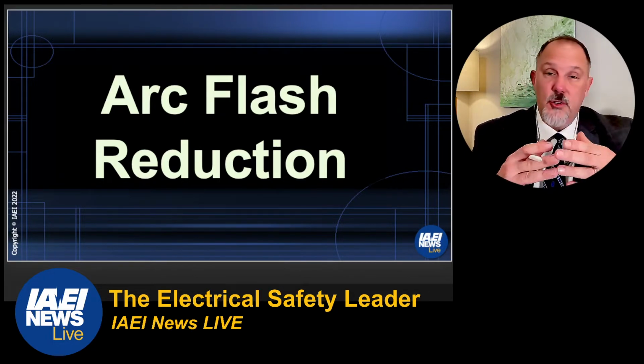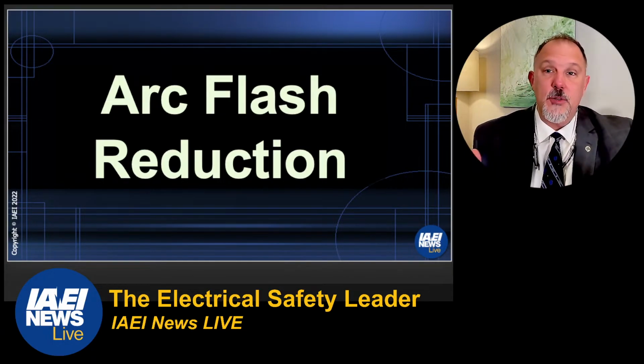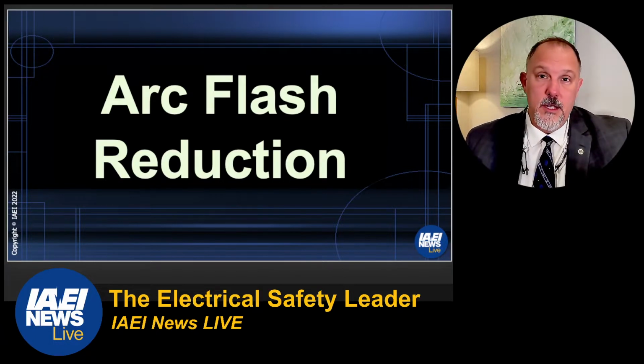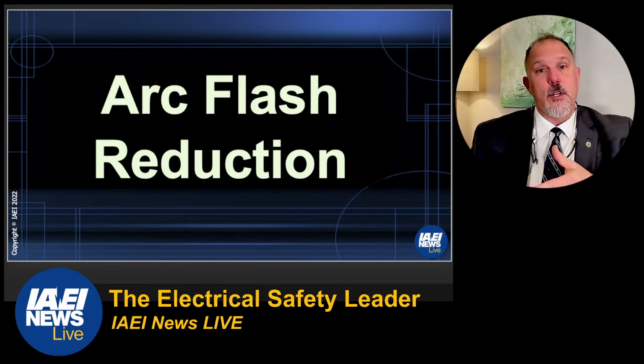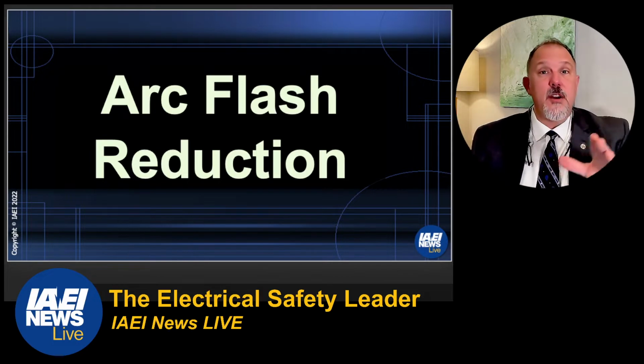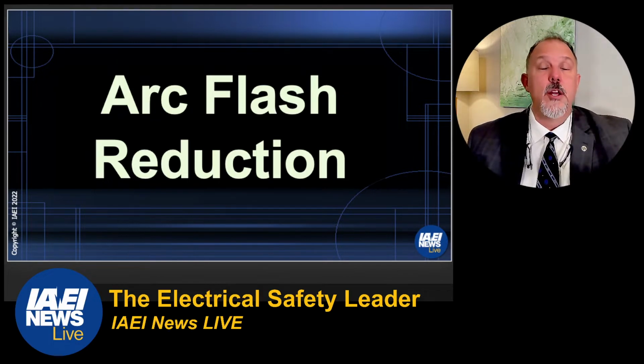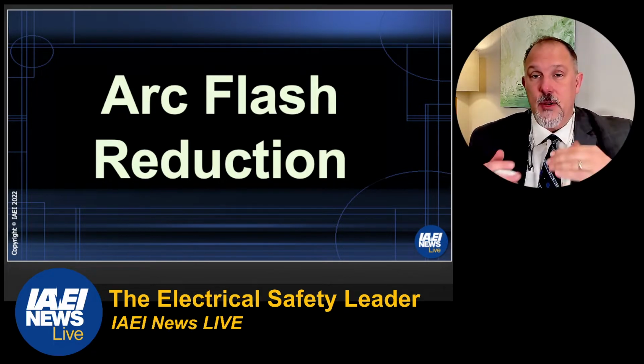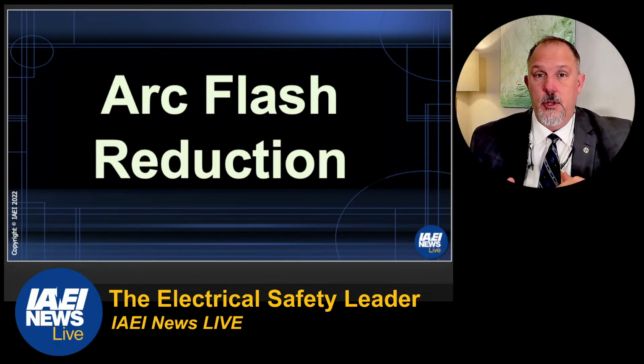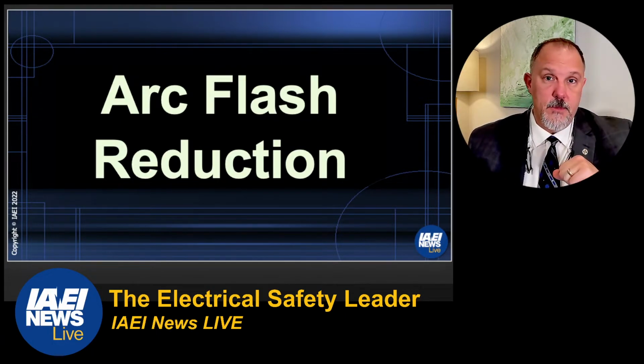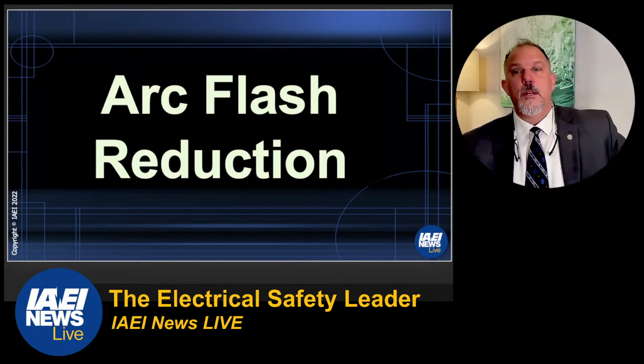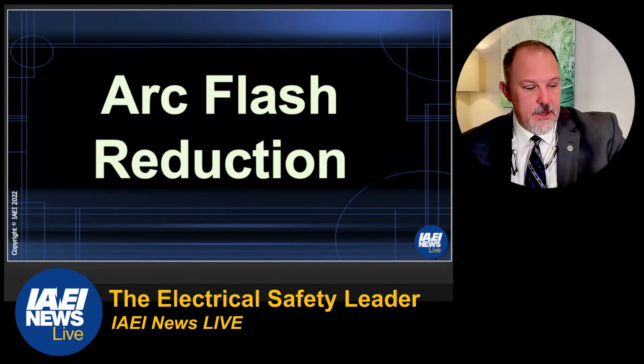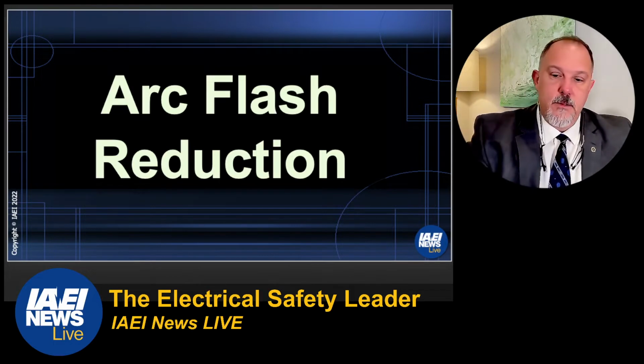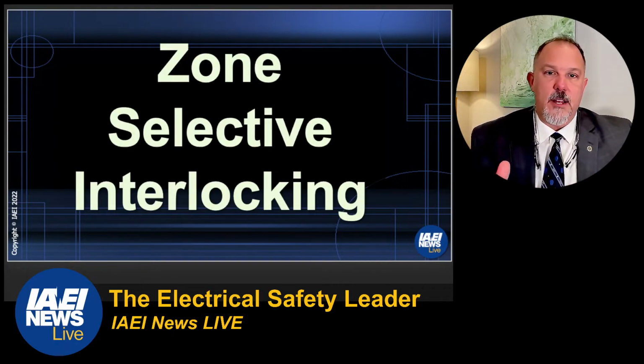You can search it on the web. IEEE 1584 is the reference that we use, and it's the primary reference. There are other references, don't get me wrong, but it is the primary reference that we use to calculate calories per centimeter squared. Now, remember I said zone selective interlocking was around before we knew what arc flash was.